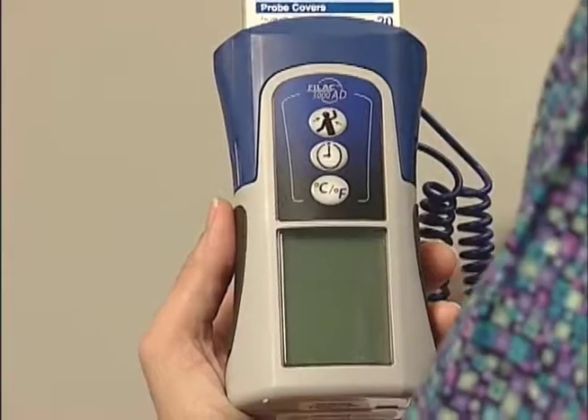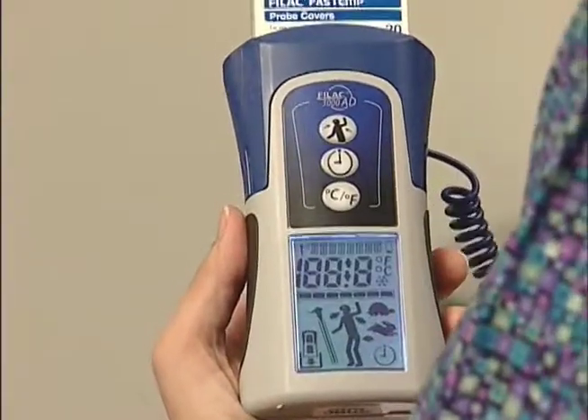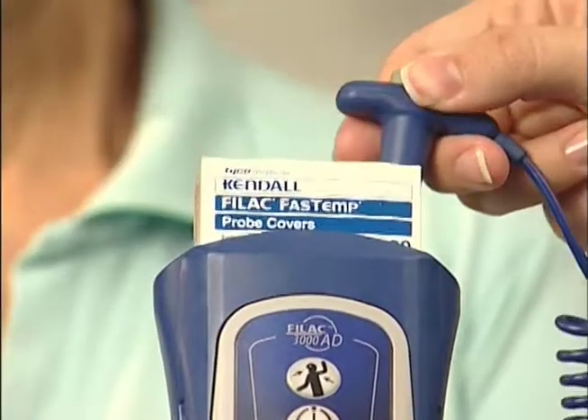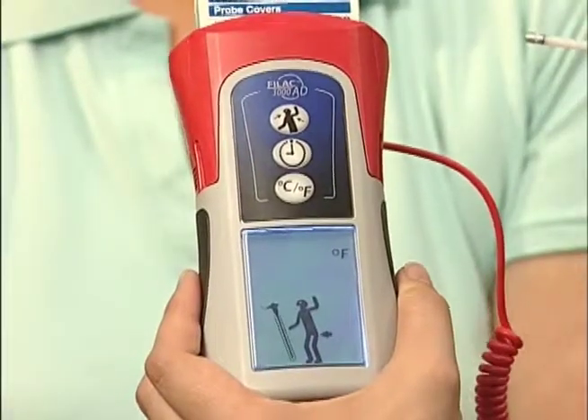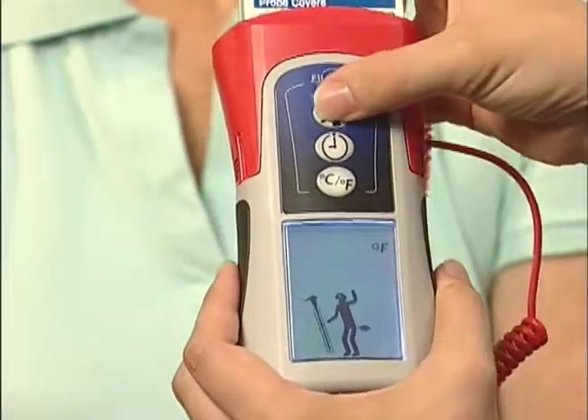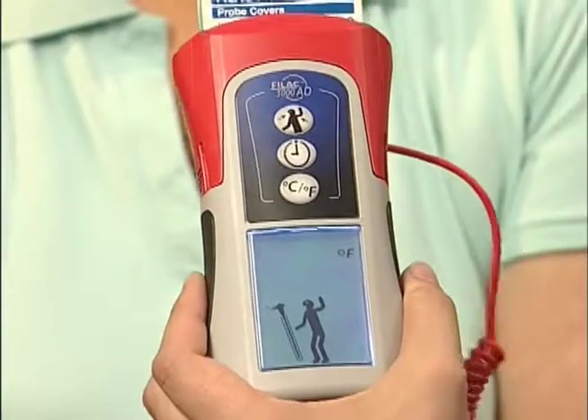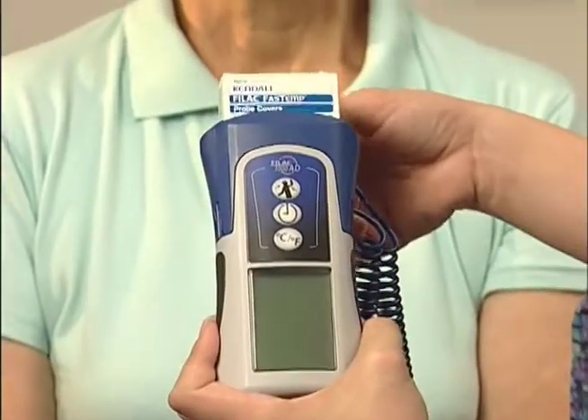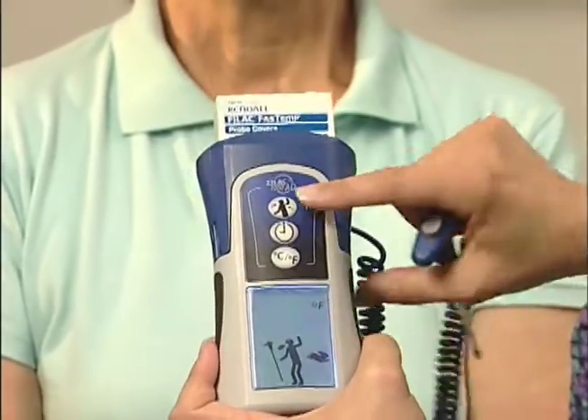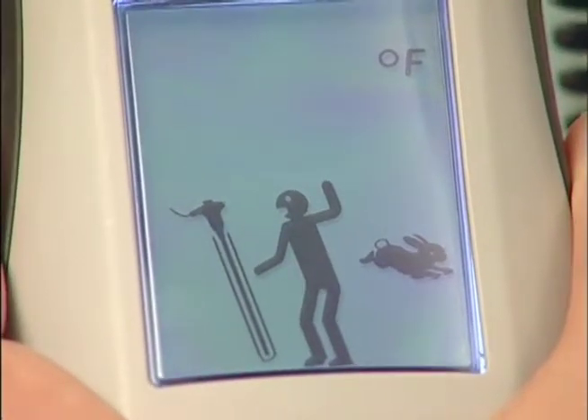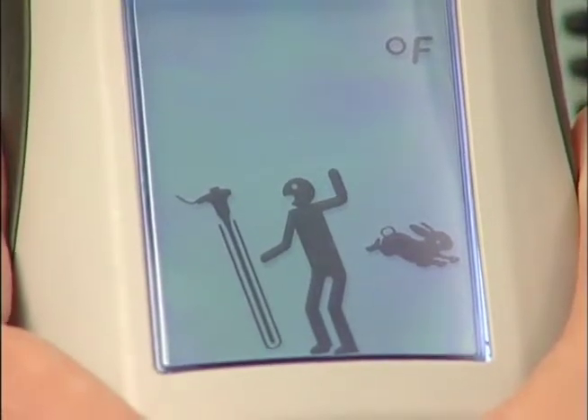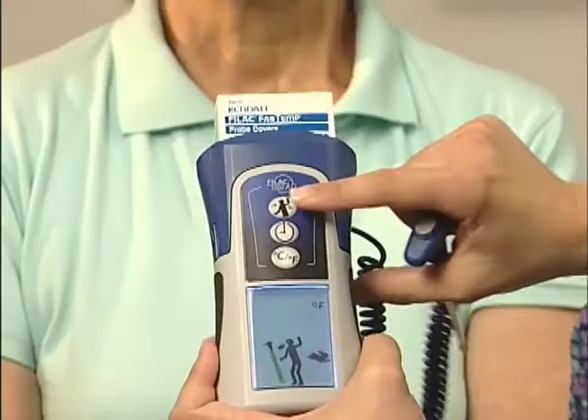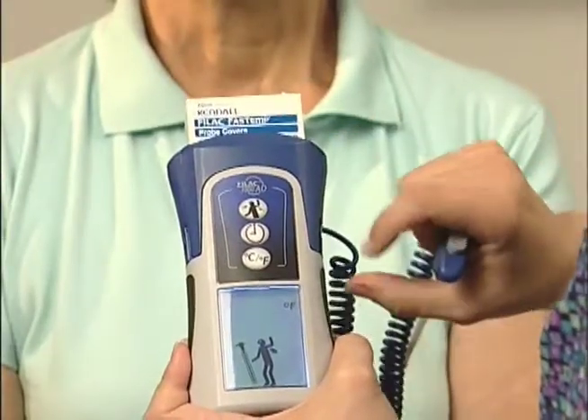An icon identifying oral, axillary, or rectal mode is displayed. The rectal icon cannot be displayed when a blue isolation chamber and probe is attached. Conversely, the oral and axillary icons cannot be displayed when a red isolation chamber and probe is attached. To take an oral temperature, use the blue isolation chamber and ensure the thermometer is in oral mode. To change the mode, press the site button to toggle between oral and axillary modes.